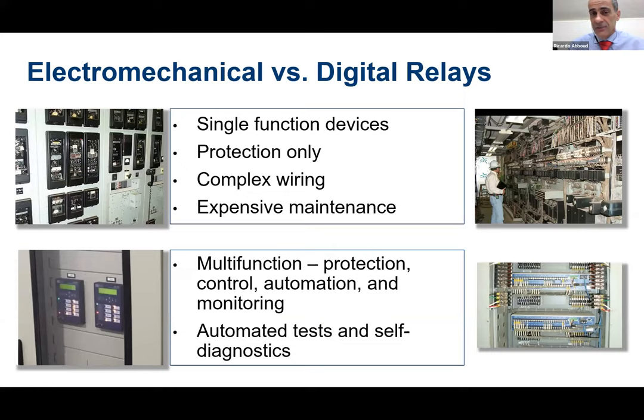So just to give a very quick overview comparing the electromechanical and the digital relay technologies. We can say that for the electromechanical technology, what you have are single devices or single function devices. So usually one device will perform a single function, for instance, an overcurrent relay is just an overcurrent relay. Overvoltage or undervoltage is just an overvoltage or undervoltage device. They perform just protection. They are not going to perform control. Okay? So to perform control, you need to have additional devices. You need to have additional control switches and so on.